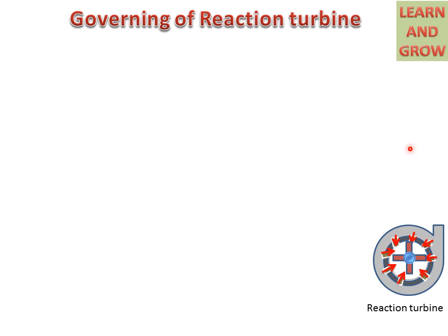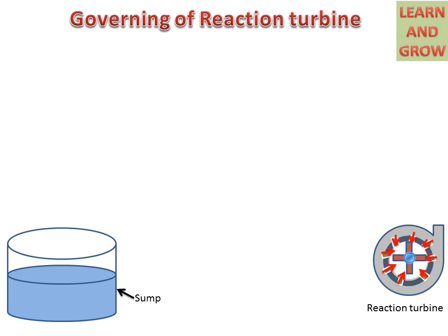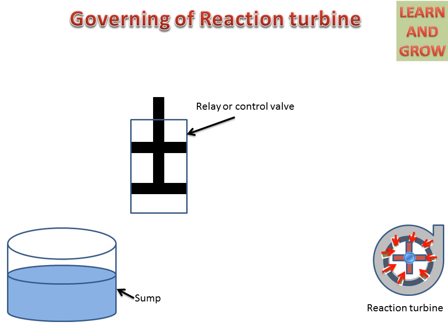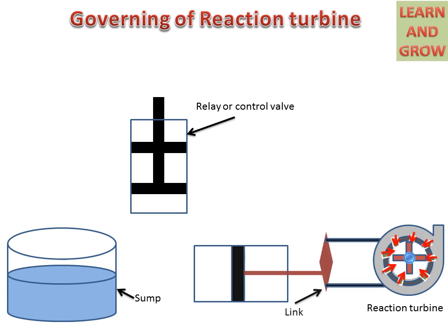First, we will discuss the parts of the governing system of the reaction turbine. We have a reaction turbine with a rotor and guide vanes through which water enters the rotor, and a casing from which water enters. There is an oil sump, a relay or control valve with a piston and piston rod, another cylinder with a piston and linking mechanism. This linking mechanism is connected to the guide vanes system to open and close the guide vanes for regulating the flow of water.